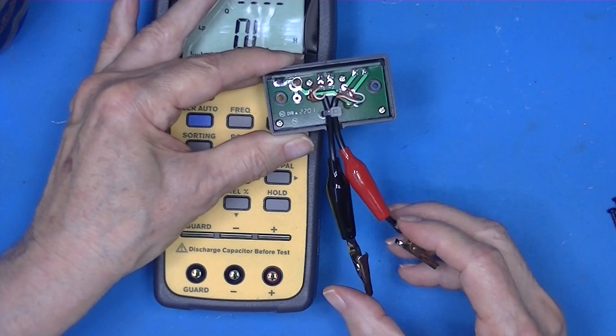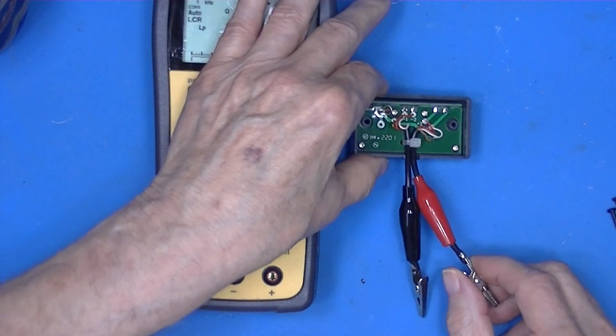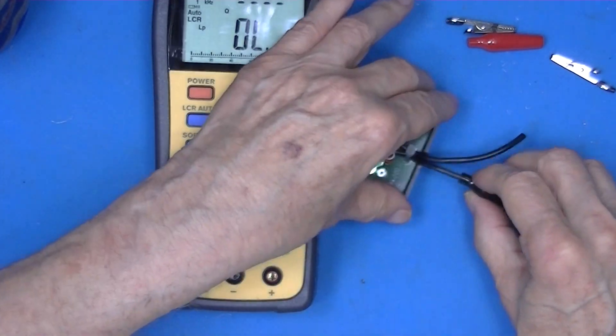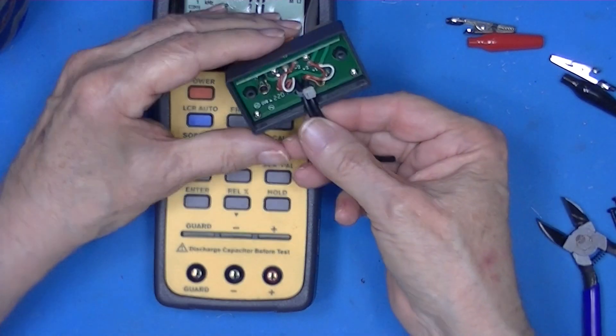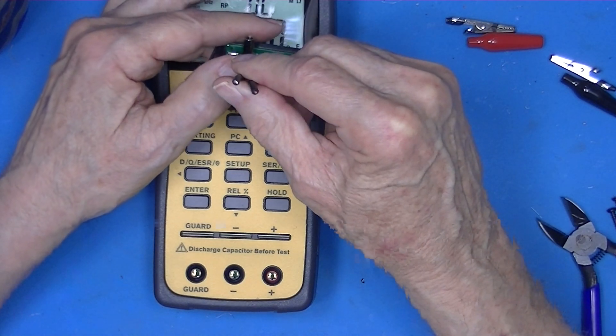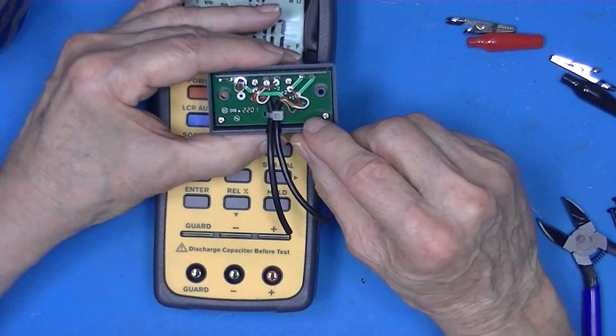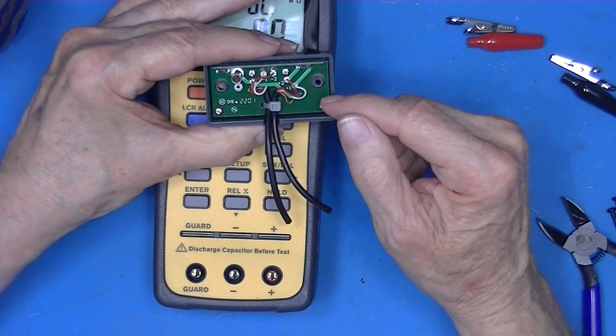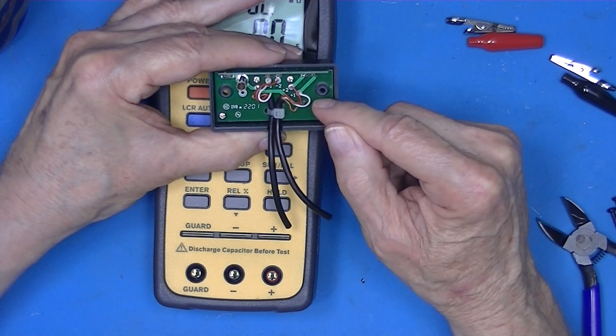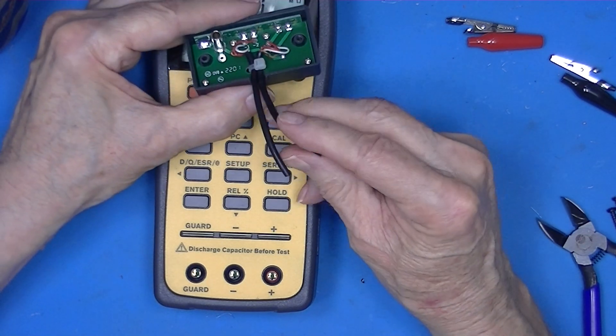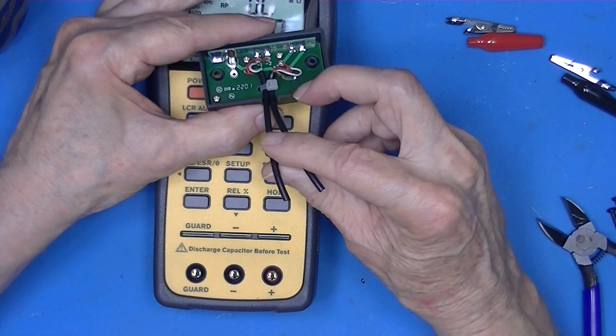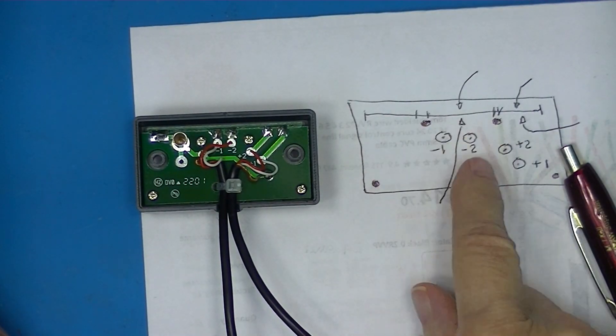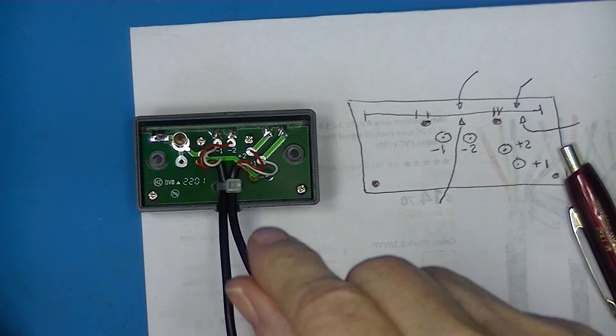To do that I'm going to cut these clips off. Now there are two pair of two wires, shielded. You can tell they're shielded because each one has a shield coming out of it. Two conductor, two pairs, each pair individually shielded. So now they're not connected together. I made a little sketch of this box and I'll put this ohm meter on sound.